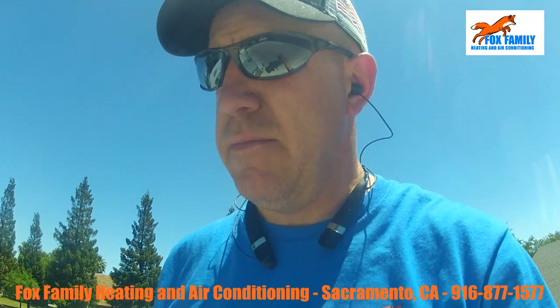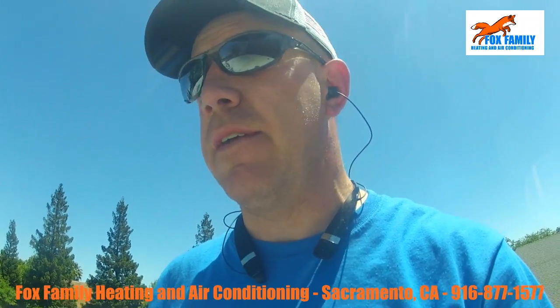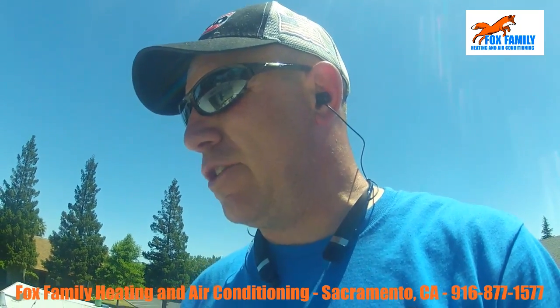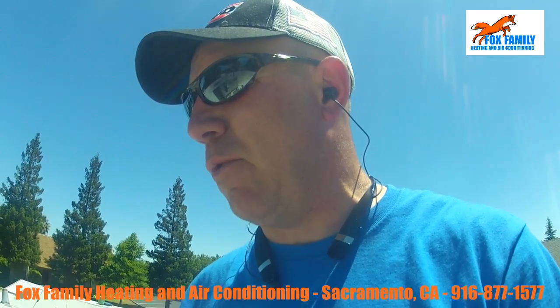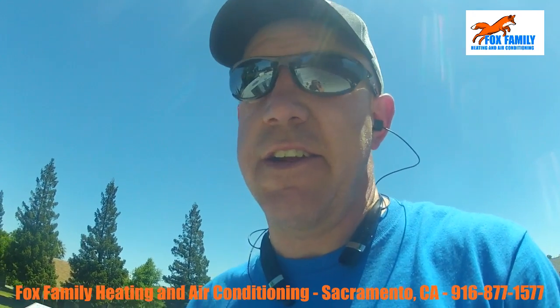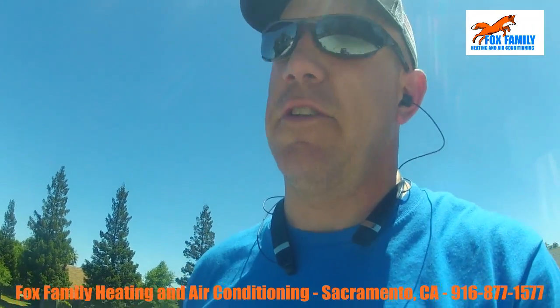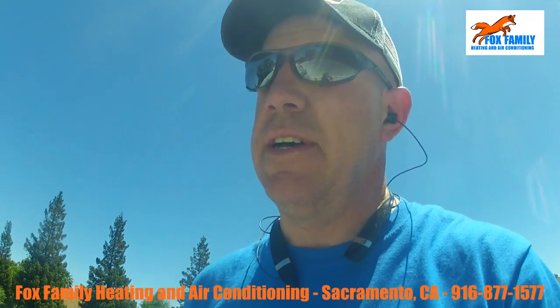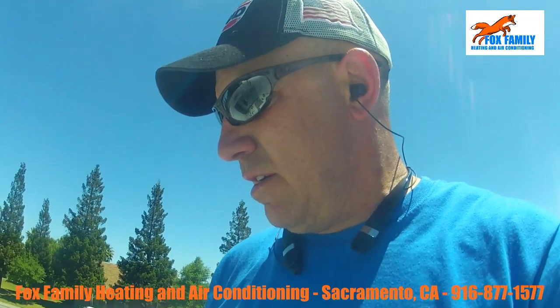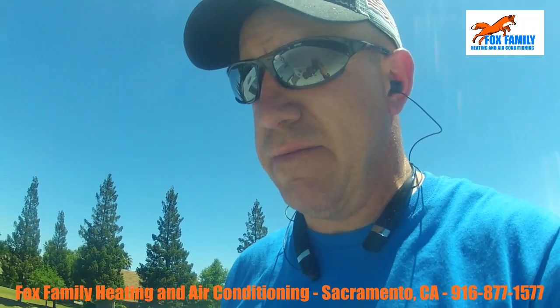Maybe the blower motor is slowing down or something like that. It could be, I don't know, I guess it could be an overcharge, but I like those pressures actually right where they're at. 110 on the high side, 110 degrees, and it's a 90-degree day today on this rooftop, maybe 95, so that's still only 15 degrees up. So I think this will fix it.